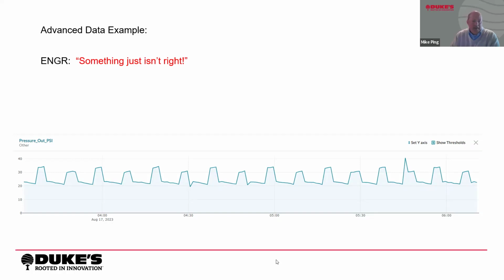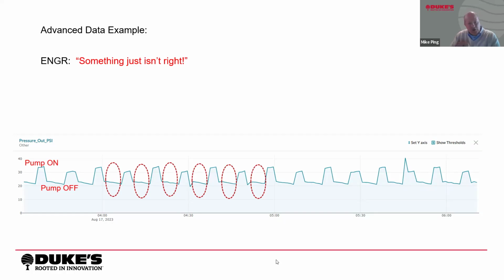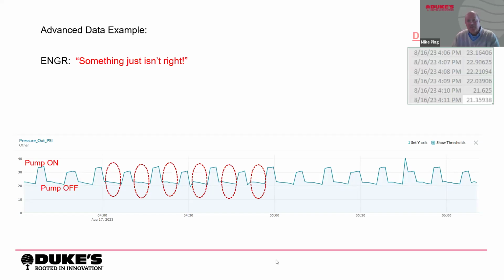I ended up looking at the output pressure. In this case, the pressure sensor was on the downstream side of the check valve. Digging into this, I saw that the pump turns on, the pressure goes up, the pump turns off, and since it's on the discharge side of the check valve, it's seeing the static head. Looking closer at those circles, it looks like it's decreasing just a little bit.